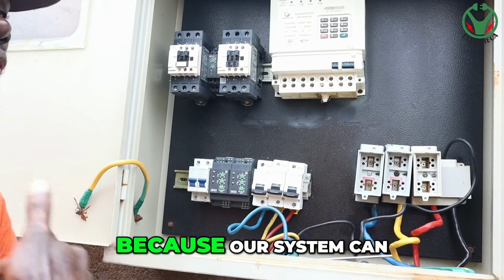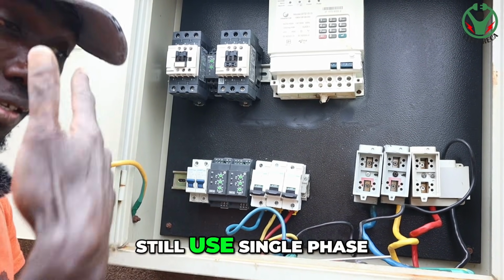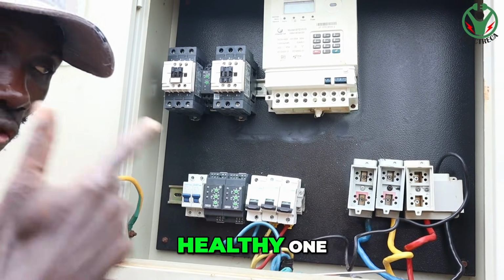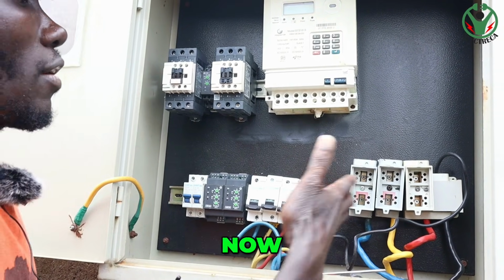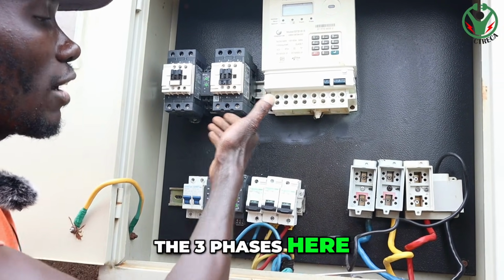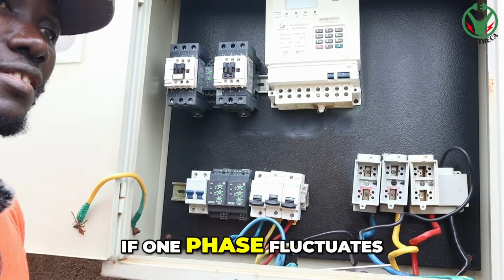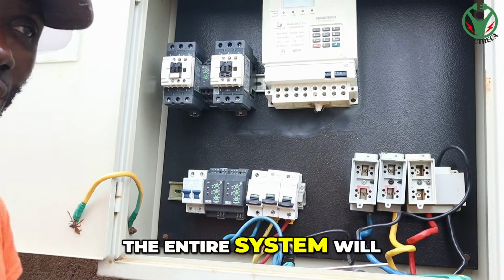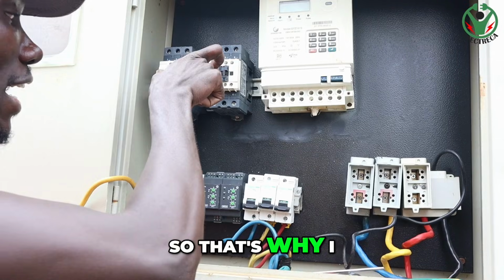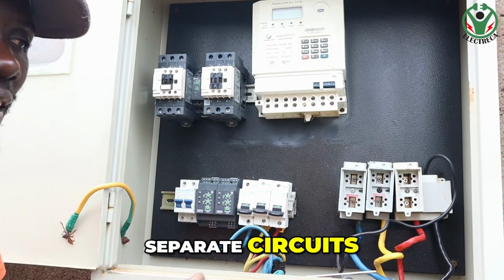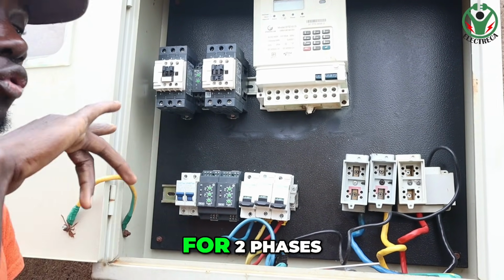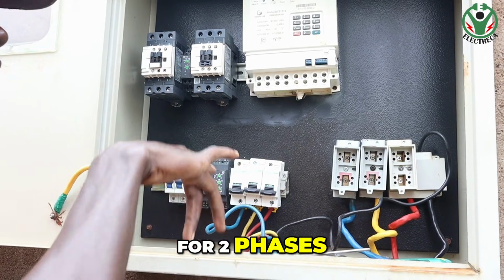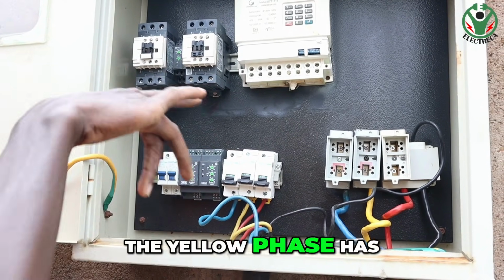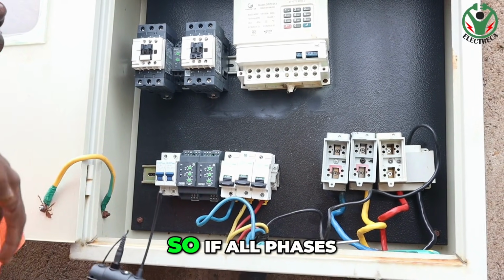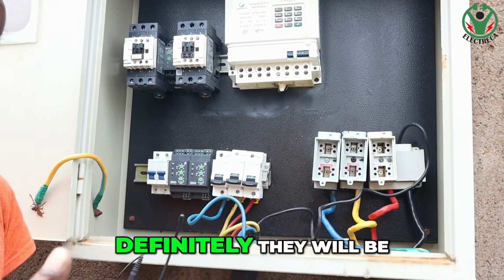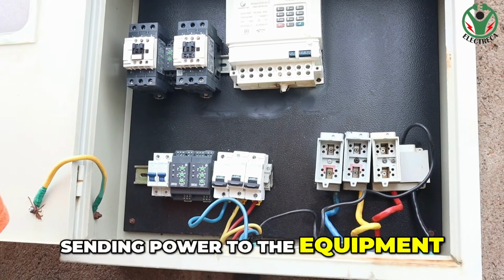Why? Because our system can still use single phase if it's the most healthy one, okay? Now, if I feed all the phases here, and one phase fluctuates, then it means that the entire system will go off. So that's why I have to put two separate circuits for two phases, okay? So the red phase has a circuit, the yellow phase has a circuit. So if all phases are healthy, definitely they will be sending power to the equipment.